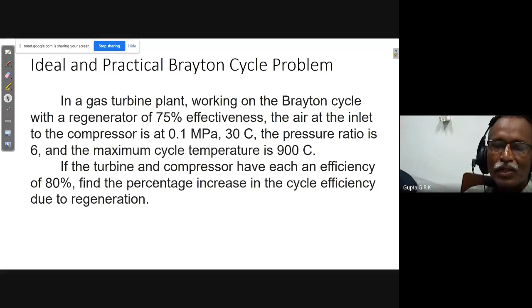And not only in the combustion chamber—if you have a heat exchanger, one side air is going and it loses some pressure, and on the other side gases are going and it loses some pressure too. If you see these lines, I lose 2 steps of pressure: one in the combustion chamber and one in the heat exchanger on the air side.